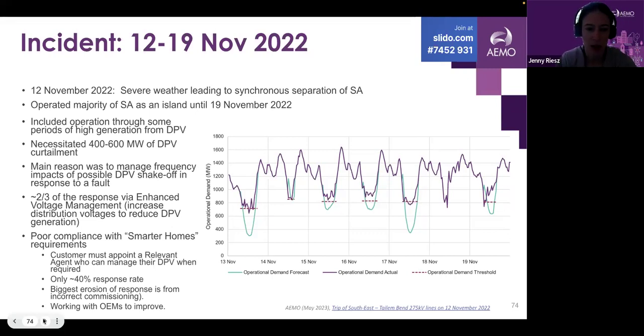Most of this response was delivered by the DNSP, our distribution network provider, through what they call enhanced voltage management, which they use to increase distribution voltages to about 1.03-1.04 per unit to deliberately trip off PV generation in these periods. That was implemented as a last resort mechanism. It's obviously not ideal to increase distribution voltages higher than nominal, but it was put in place to deal with legacy PV systems that didn't have active controls. In this event, it was extremely effective and a crucial lever to maintain security.